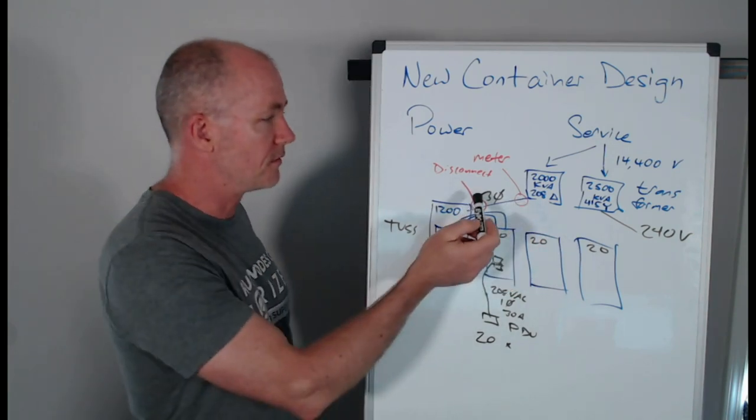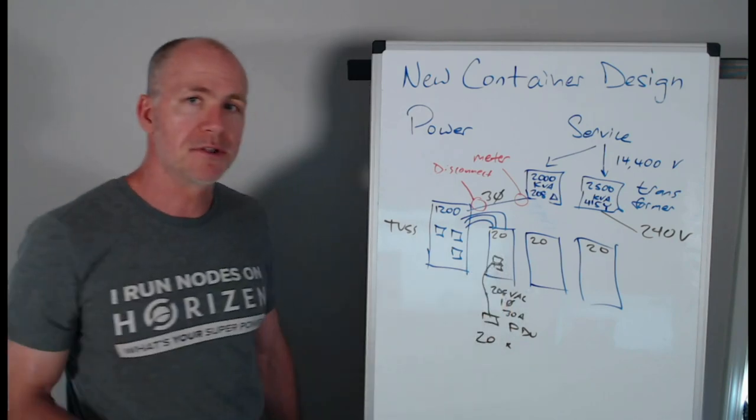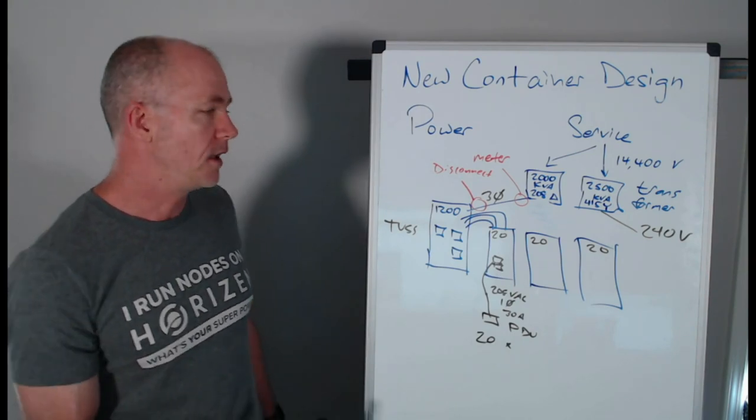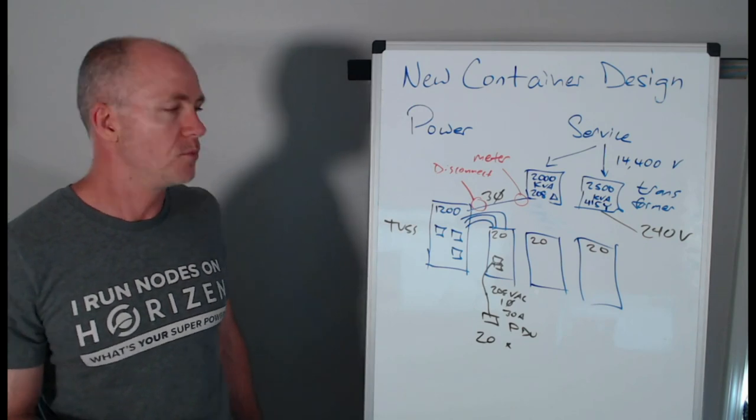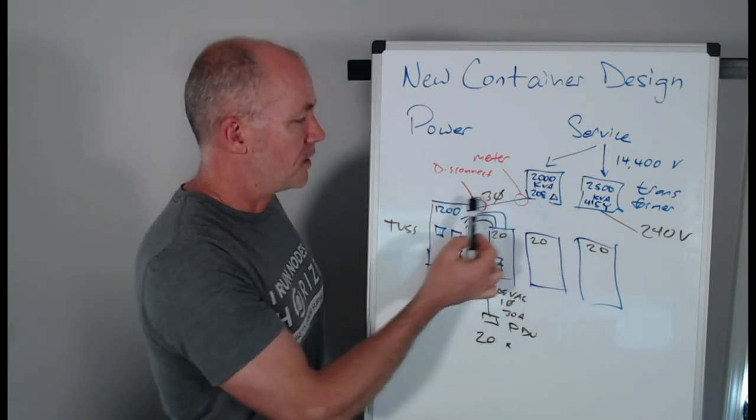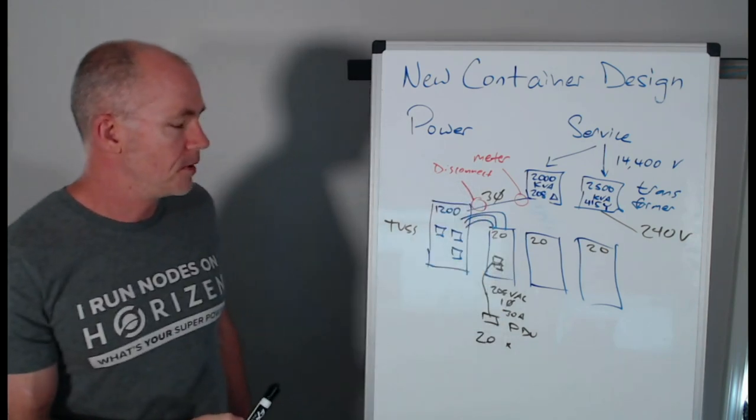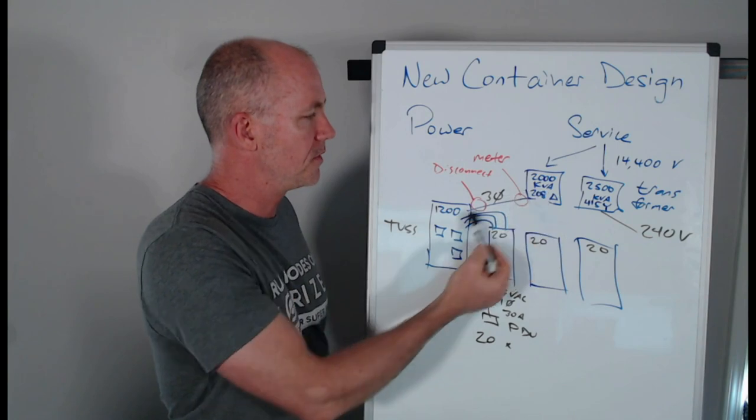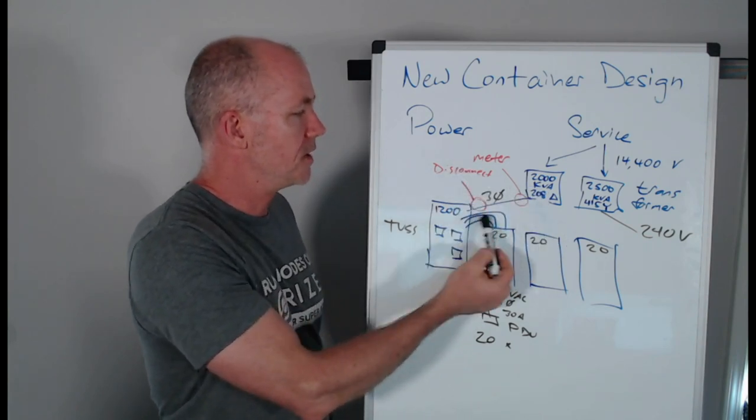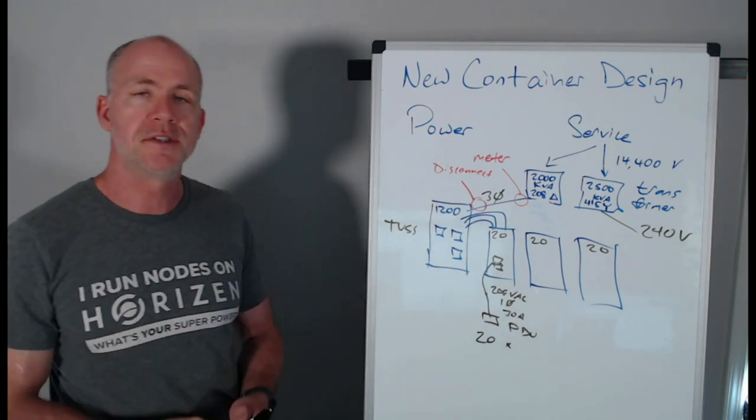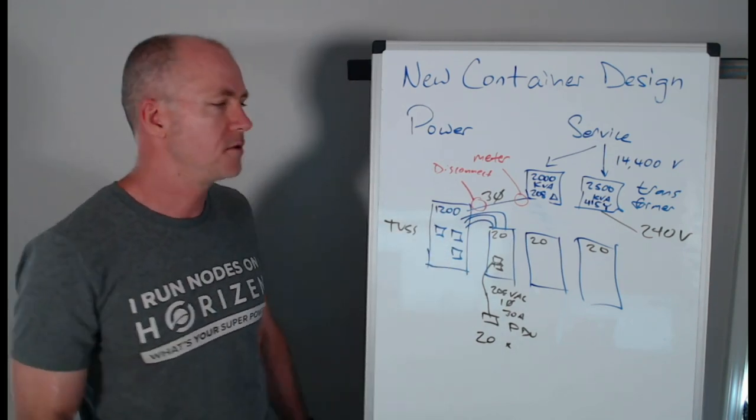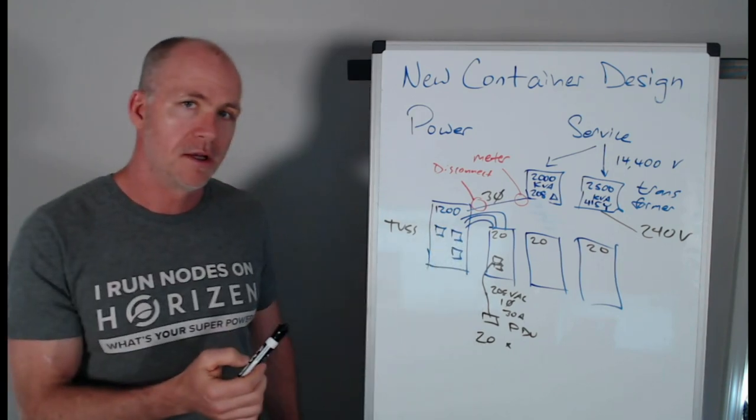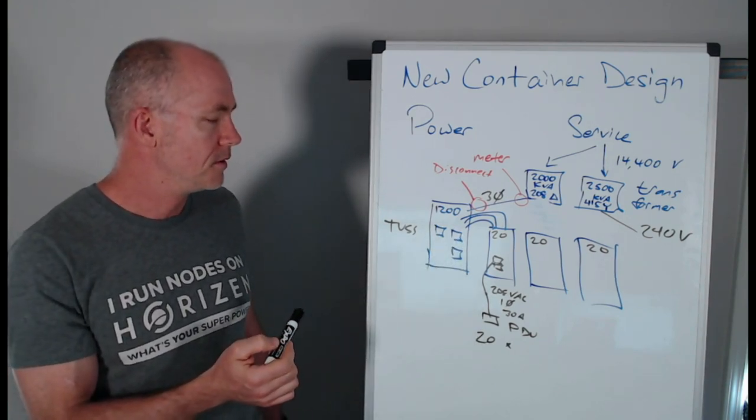Delta is because we're going to connect phase to phase. And when we connect phase to phase, we'll get 208 volts AC, but it takes two breakers to do it. So it takes a little bit more electrical wiring, but we don't get the efficiency in the panels that we want. But that's the way it is. Sometimes you got to work with what life hands you. So within this connection for a single one of our 1200 amp panels here, we will have the power company bring in the transformer. They'll hook a meter into it. There's three phase cabling that comes in. There's a service disconnect on the outside of the building. If there's a fire inside, it's nice to be able to come and disconnect the electricity on the outside. And then that comes to 1200 amp three phase panel here, where we have three 400 amp breakers.